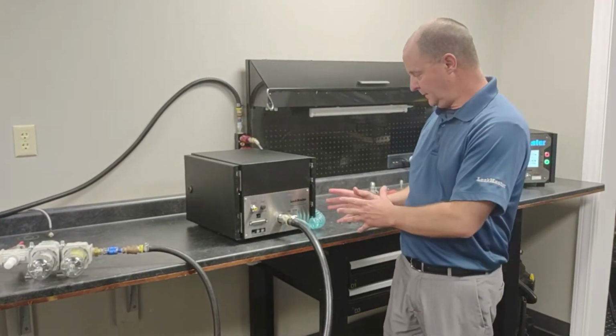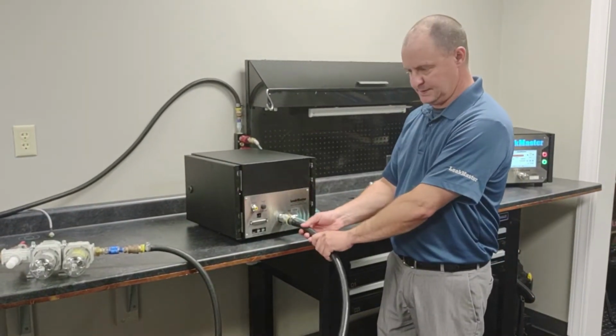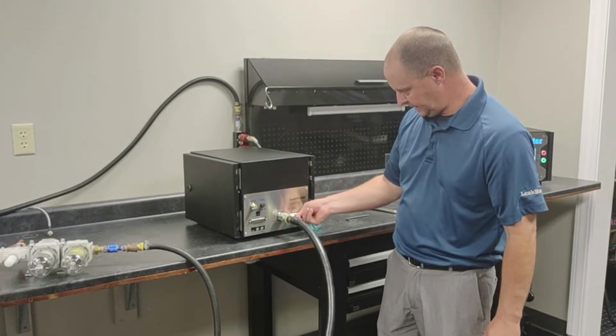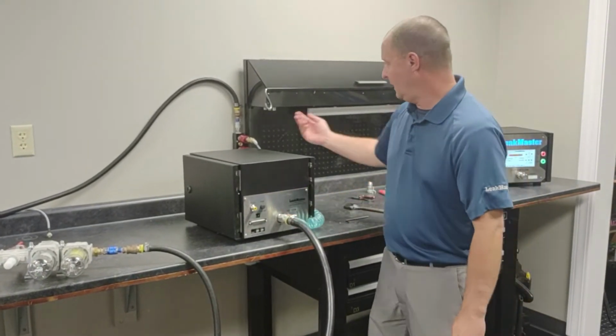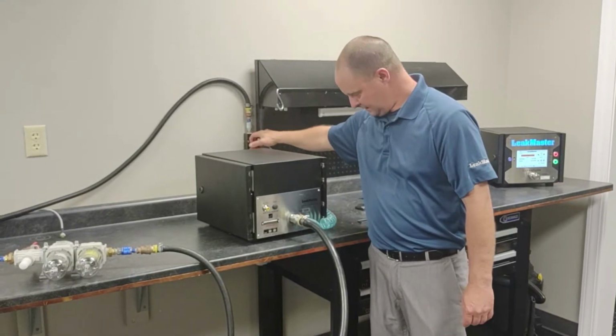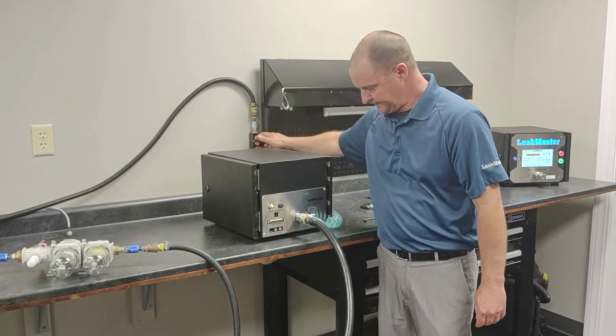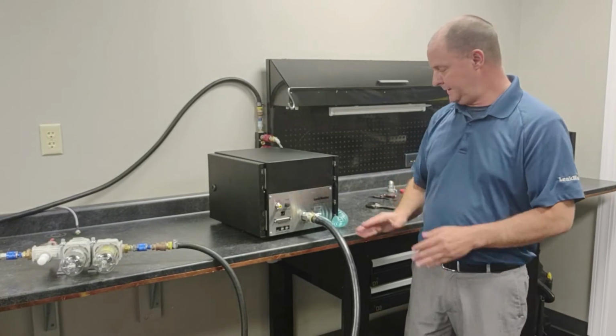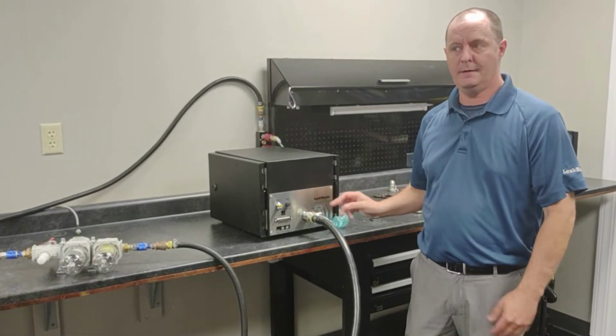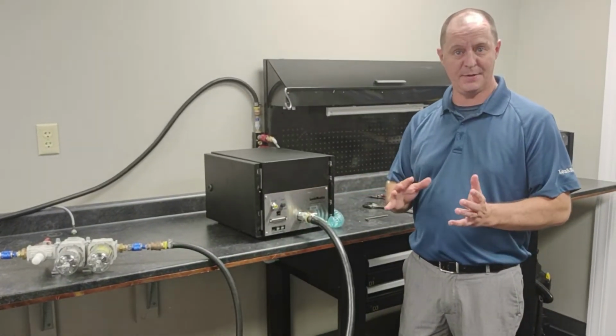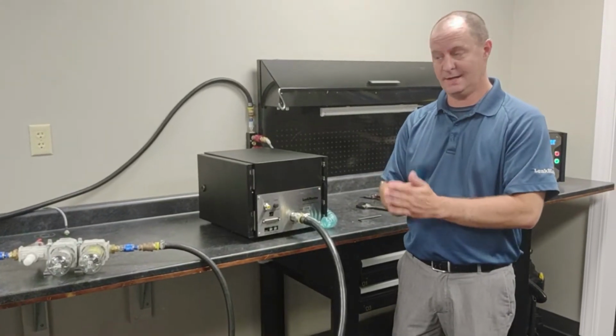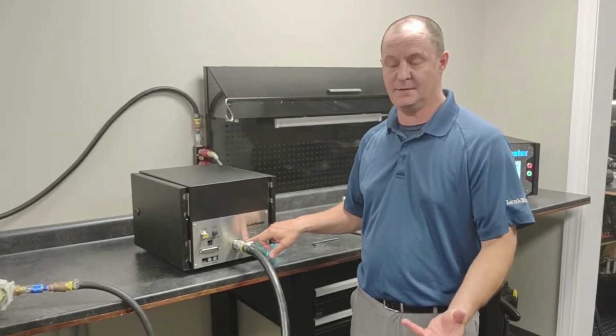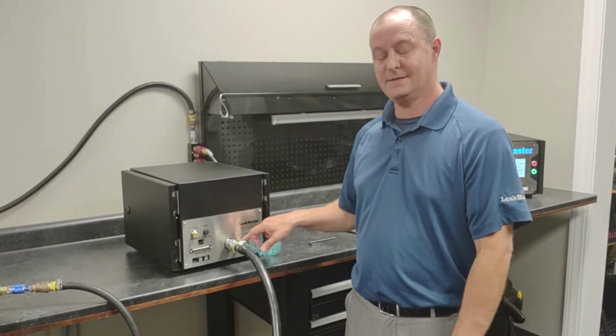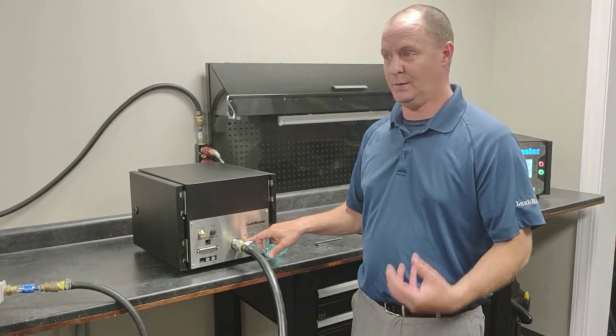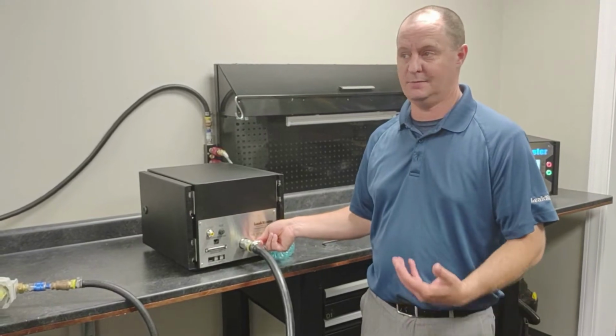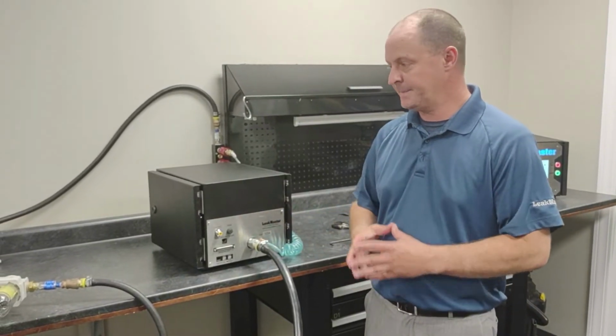So now that we have the unit plumbed up, we've got the air source to supply the test manifold, and we've got a pilot pressure source. First thing we're going to do is bring air onto the pilot pressure port. I would also recommend that this always has air on it. So in the event of an e-stop on your machine, if there's any possible way that you can keep air pressure on this and still have your machine be safe, that is the recommended way to do that. We don't want to be dumping air off of our pilot pressure really at all if we don't have to.